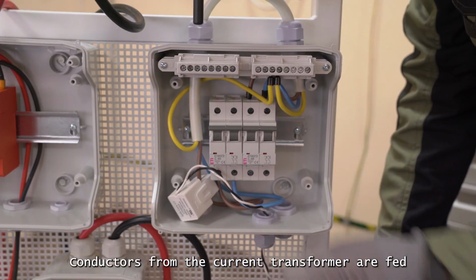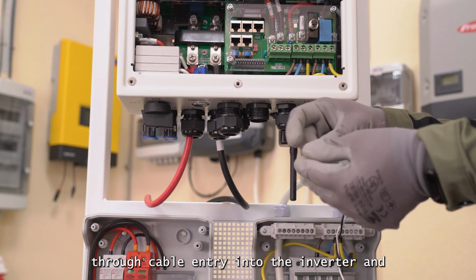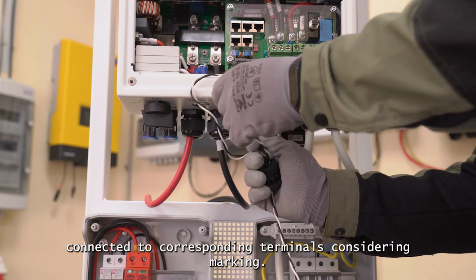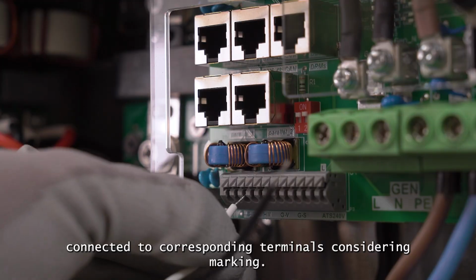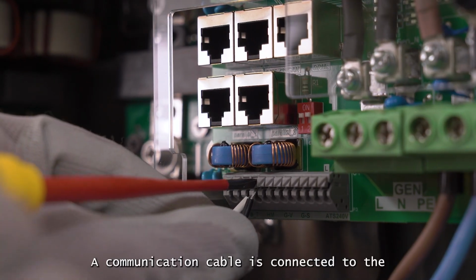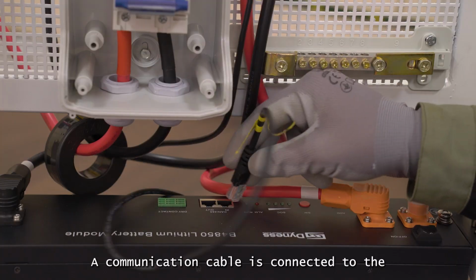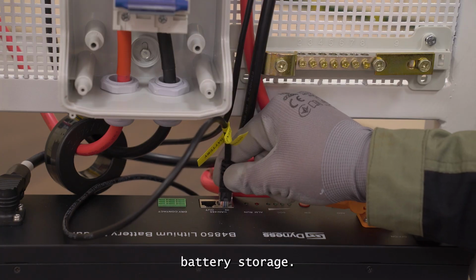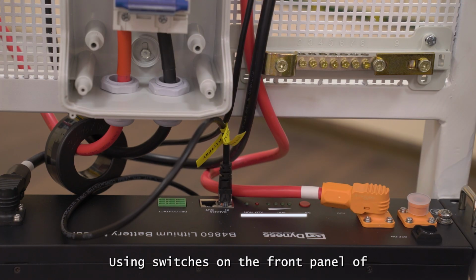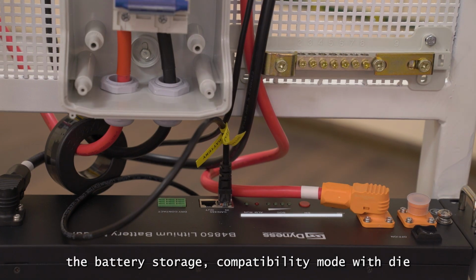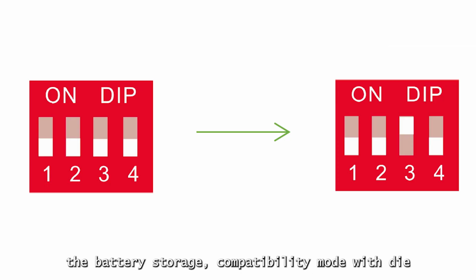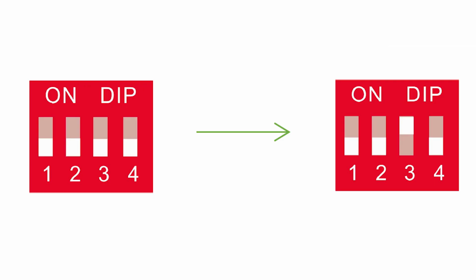Conductors from the current transformer are fed through cable entry into the inverter and connected to corresponding terminals considering marking. A communication cable is connected to the battery storage. Using switches on the front panel of the battery storage, compatibility mode with the inverter is selected.